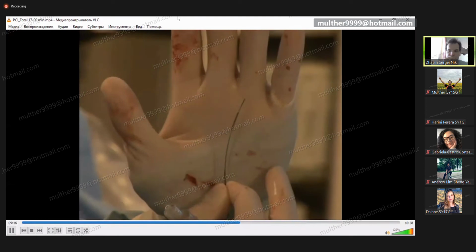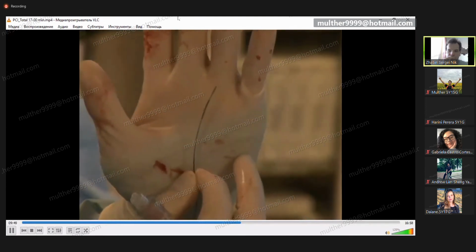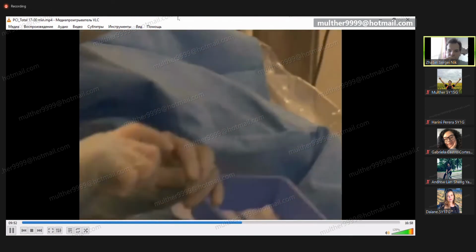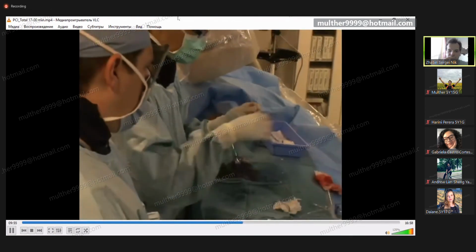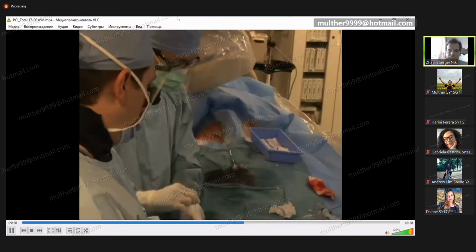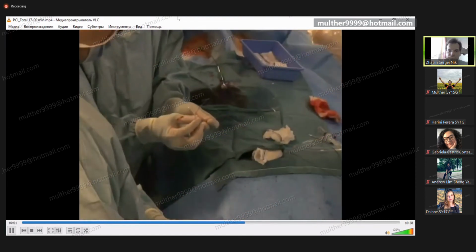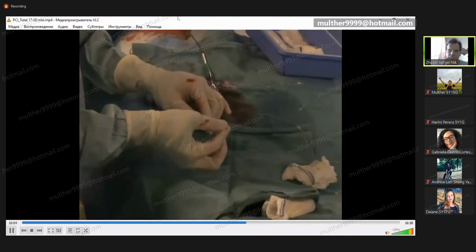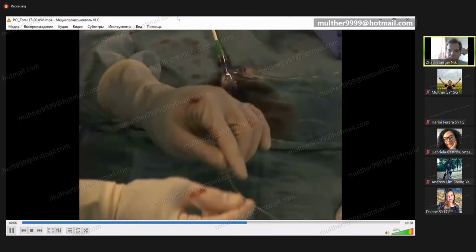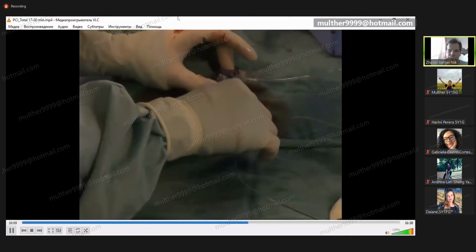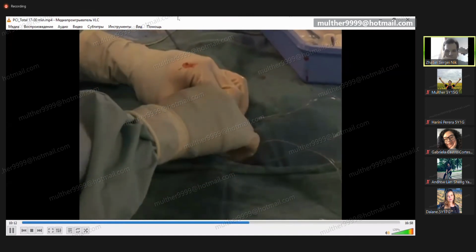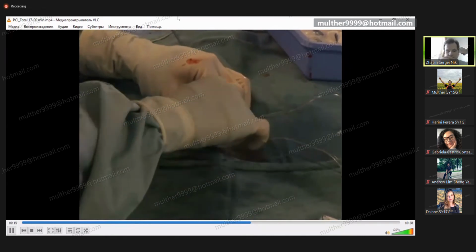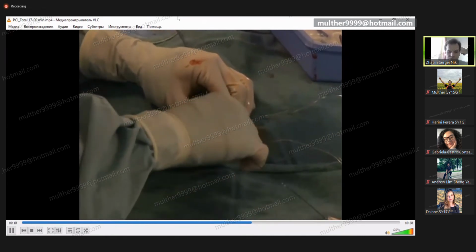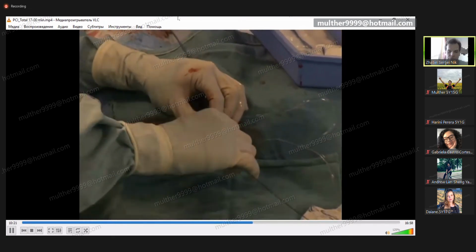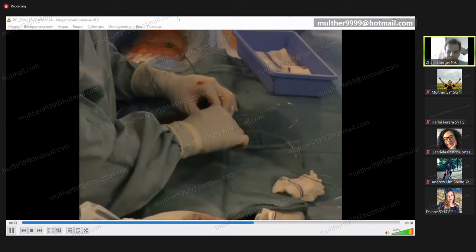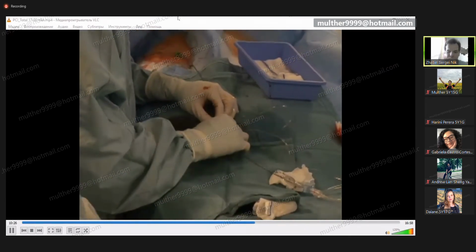Use of a stent catheter is demonstrated here. The stent is mounted in a crimped form onto a deployment balloon on the distal end of the stent catheter. Similar to the balloon catheter, the stent catheter has a short, approximately 10 centimeter length, monorail lumen through which the catheter is advanced over the guide wire. Unlike angioplasty balloon catheters, stent catheter balloons routinely are not prepped with negative pressure outside of the body, as doing so may result in the stent becoming dislodged from the balloon during advancement. The stent catheter is then carefully advanced through the guide catheter, over the guide wire, and is positioned across the lesion of interest.